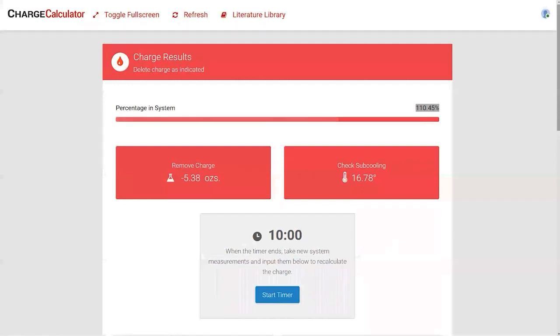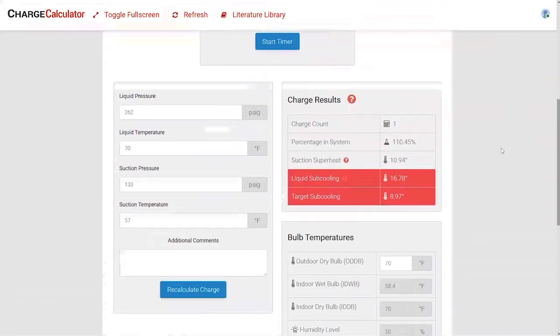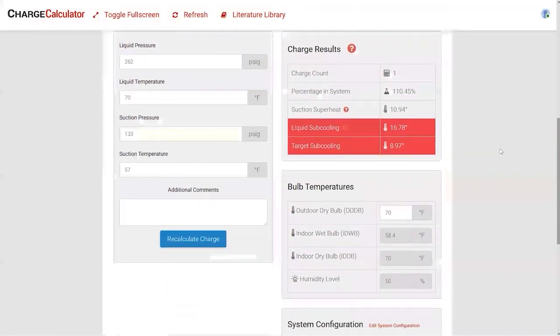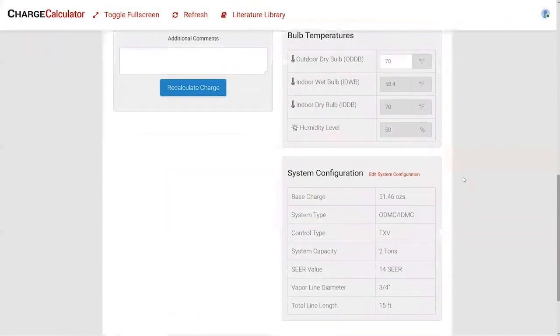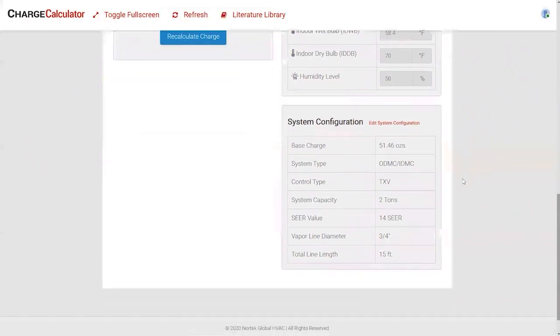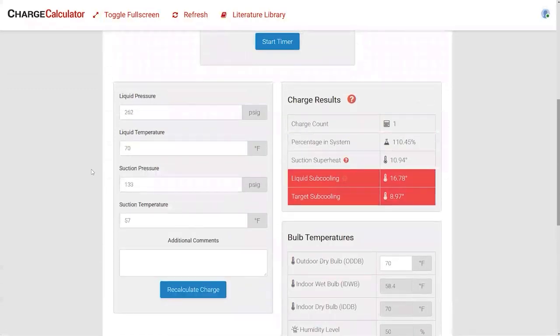Scrolling down on the charge calculator, you'll see all the pressures and line temperatures we input, the percentage of refrigerant in the system, and a summary of the system configuration we entered. If you had a two-and-a-half ton unit instead, you can go into 'edit system configuration' to update those settings. Since we're overcharged, we'll use a recovery tank to bleed some refrigerant out, then recheck the charge.